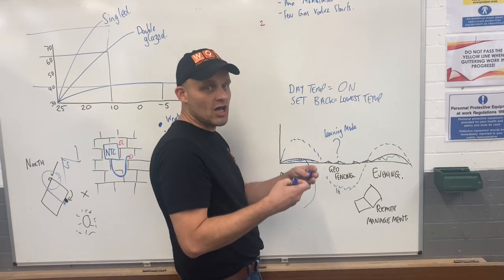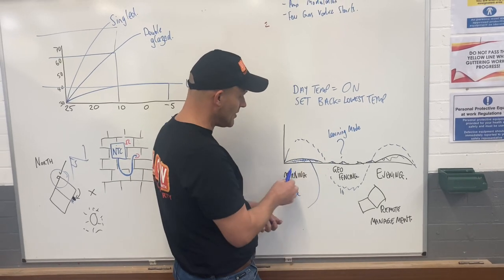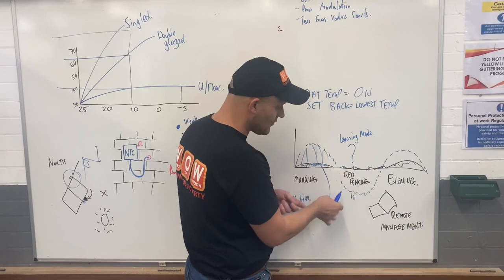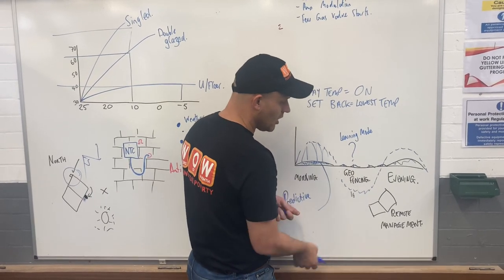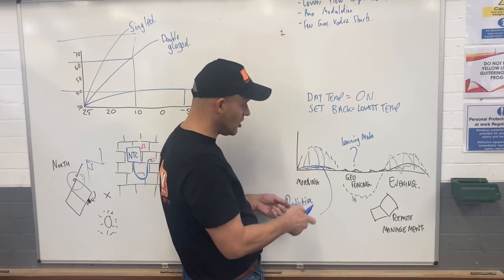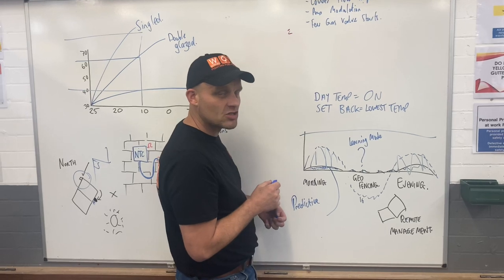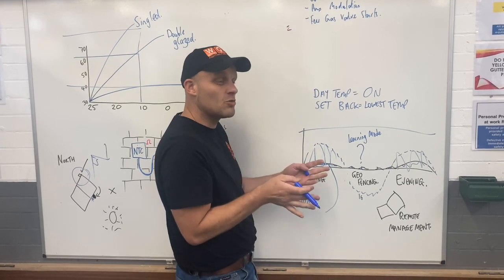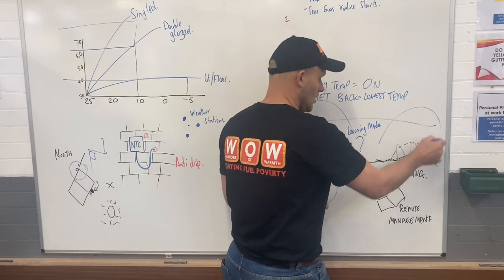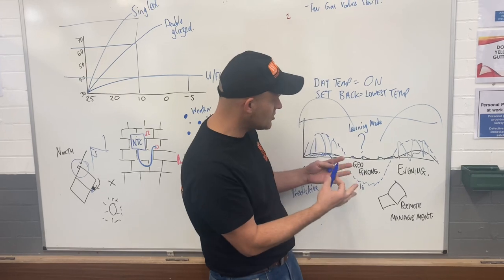Now, if you use box standard controls, room thermostat, a timer, what'll happen is the boiler will fire up, you're using all that gas, switch off, the house will go cold, it'll fire up again. So you can see the difference in this chart. Weather compensation, gas is constantly being used, low. So it's almost like having a pilot light on, isn't it? On-off controls, on, off.